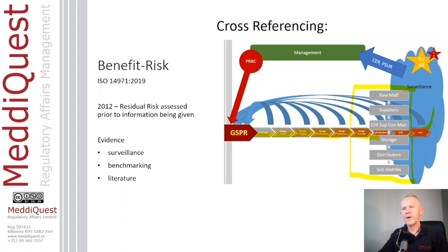When it's put on the market, we now monitor it. We monitor not just our product, but the market, so that we can show it's still state of the art. There aren't other better products out there. So benchmarking becomes an important part of surveillance as we watch how our products are used and any adverse reports that may need to get reported through our EU authorised rep if we are not inside the European Union.